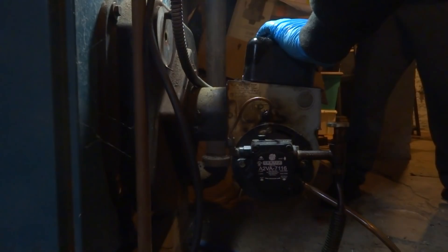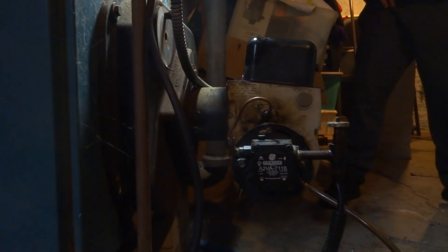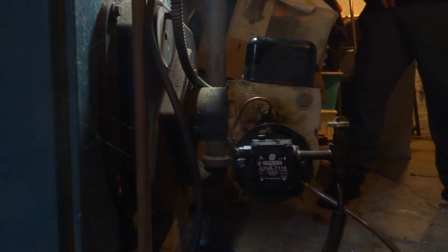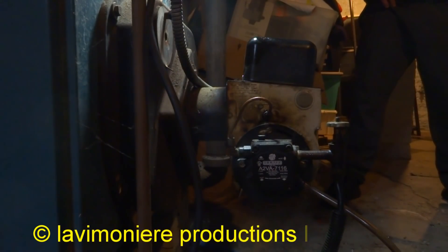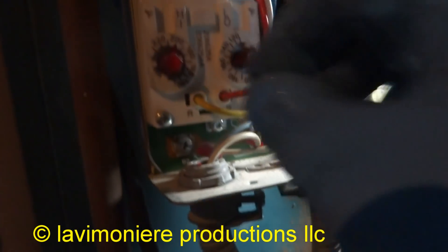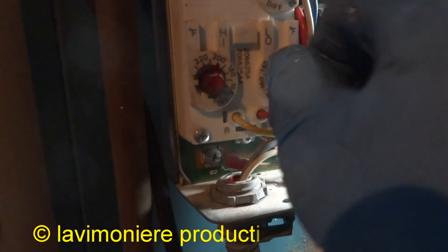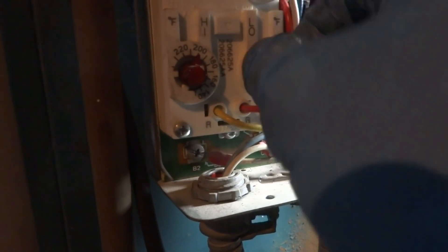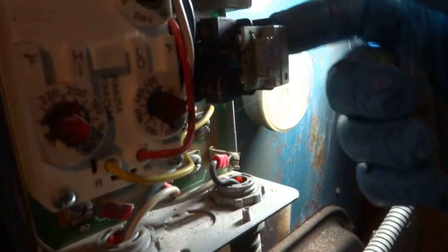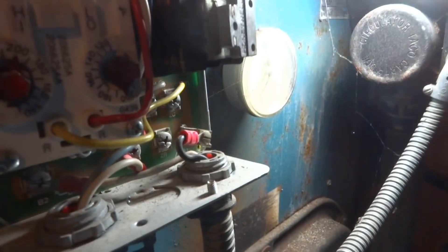See she's not firing. It's not firing — it might be a bad cad cell, unless this thing's not calling. No, it's not calling. Bad control then — the control's not calling, and we got a little limit here. Got a bad control. Hear it? Yeah. Because this isn't calling here. That's very odd.